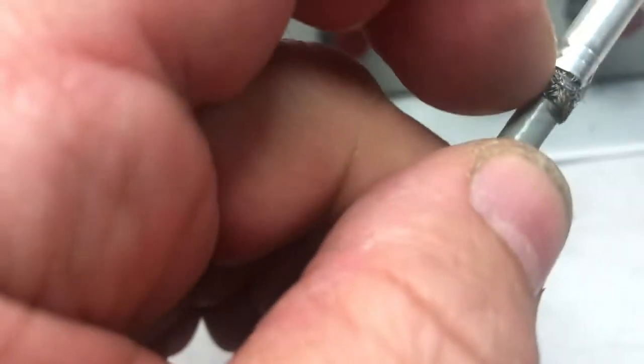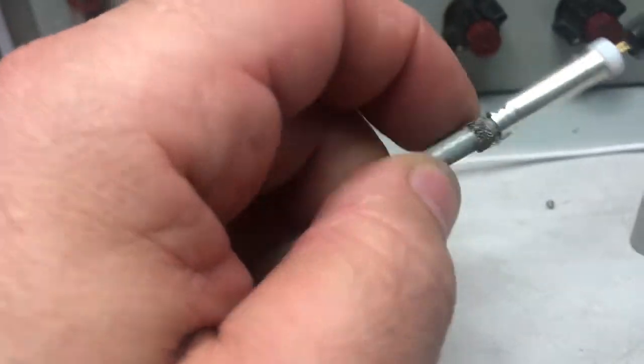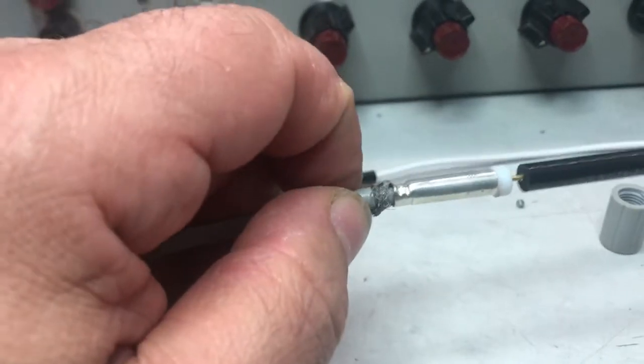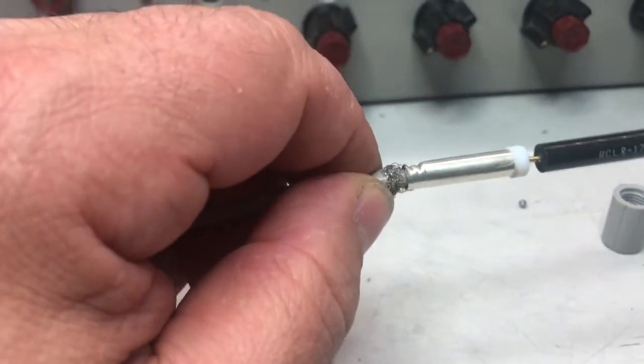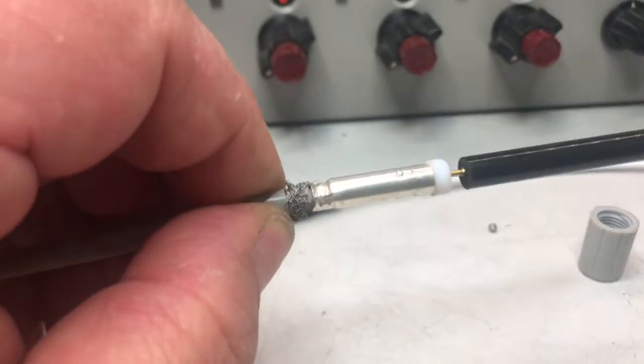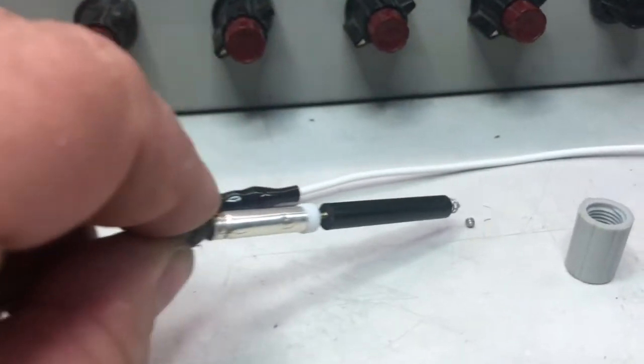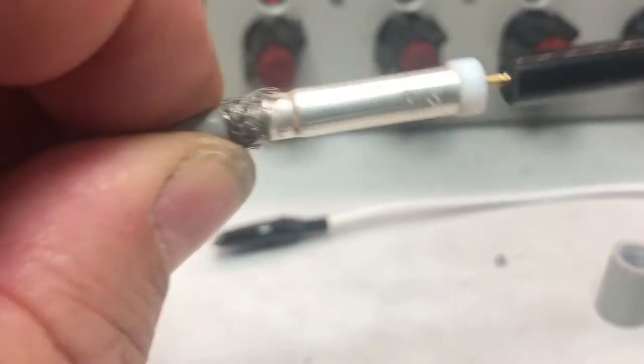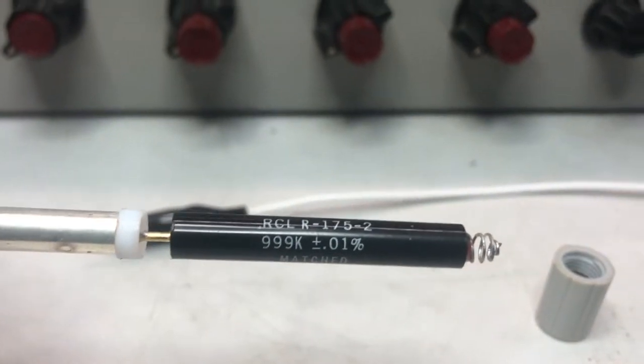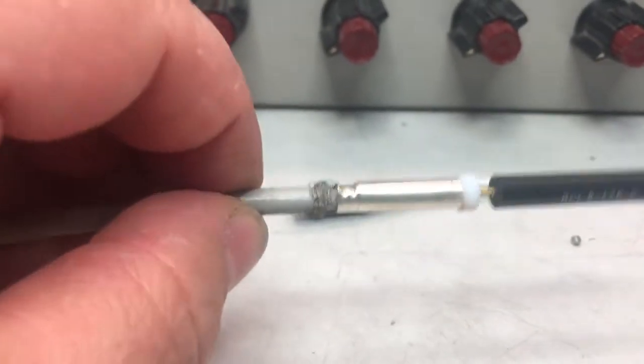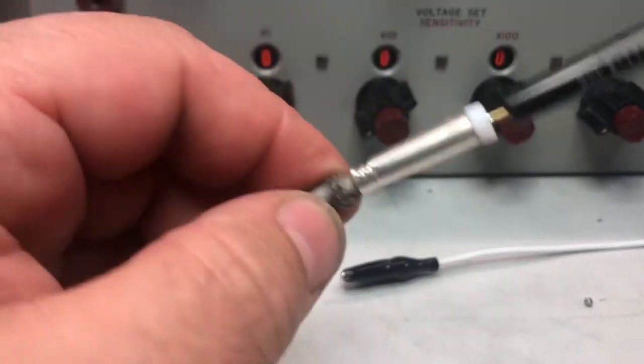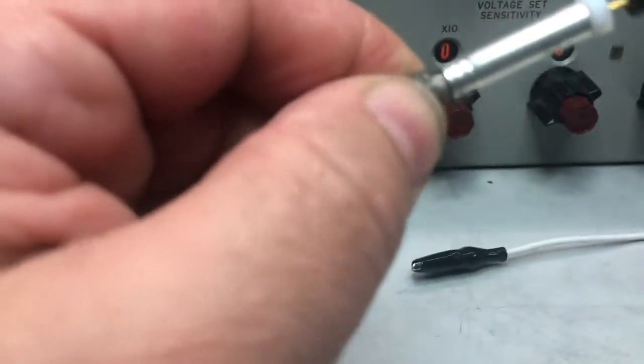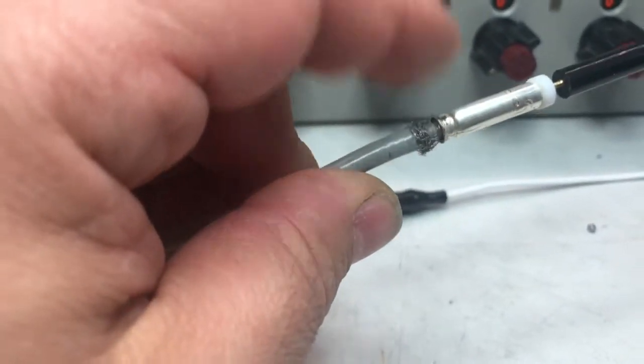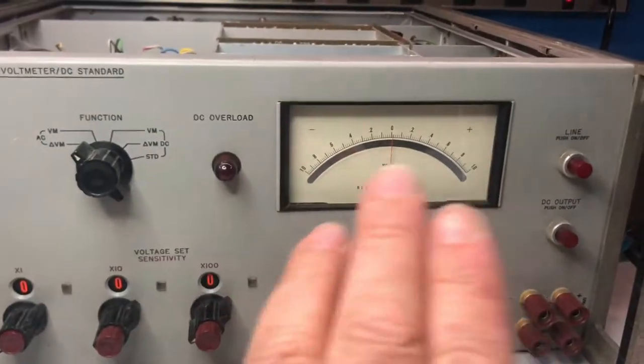And my assumption seems to be correct, and indeed it seems that the braid here slid out from this crimped part here. So I need to find a way to reattach. Moreover, it's clear that this probe has been dismantled several times. There are screw signs over there, and this should be a high precision resistor. Yeah, I believe that the AC was a problem in this instrument with this ground braid disconnected. So maybe there was a very bad contact problem and the instrument was unstable in the needle.